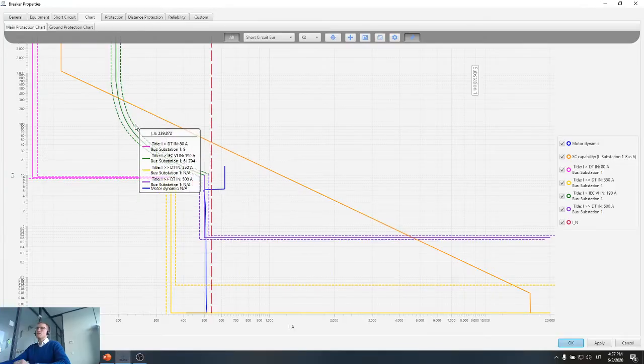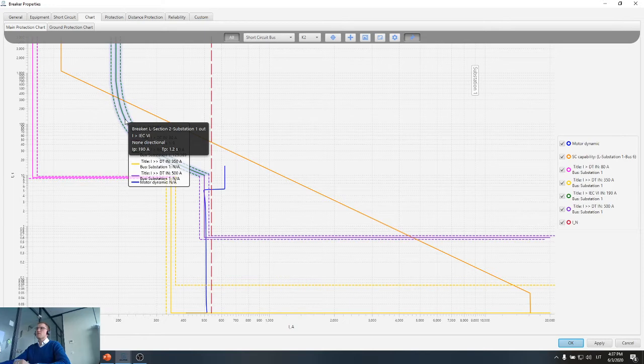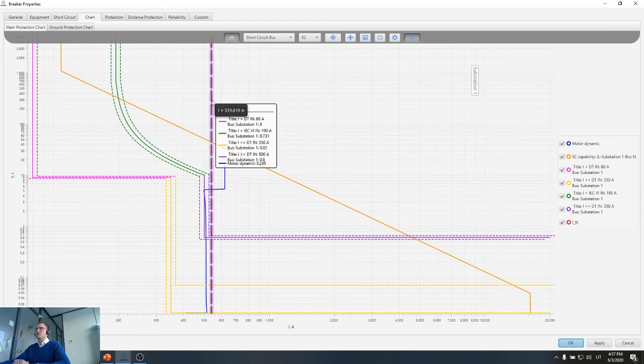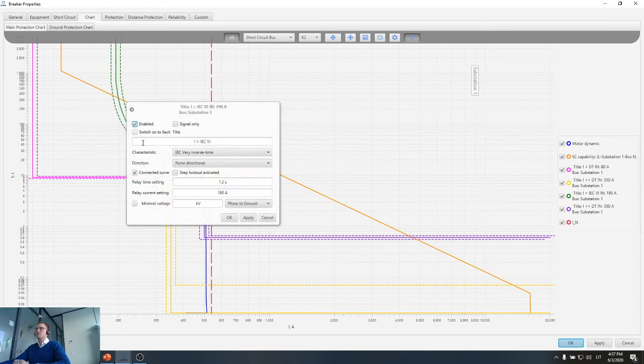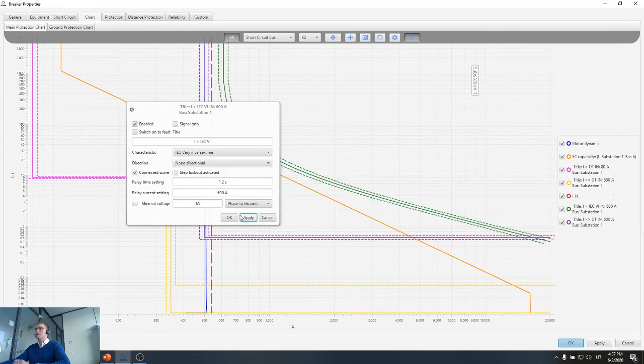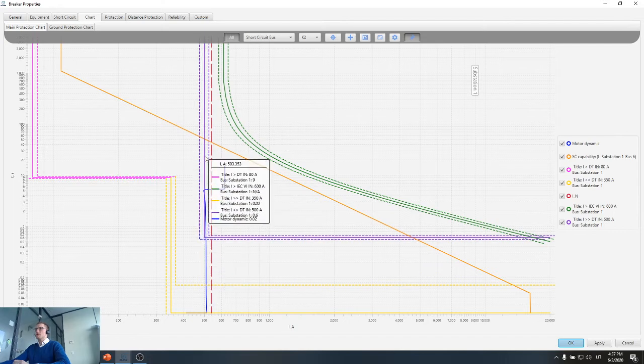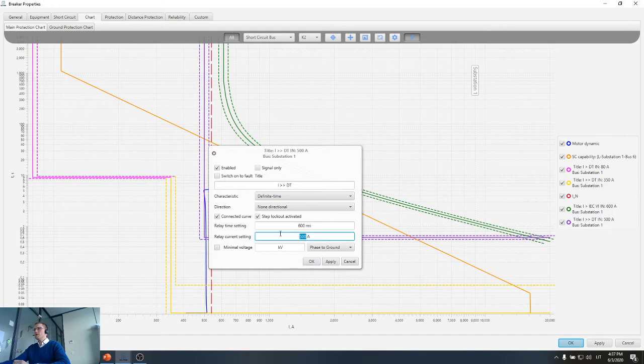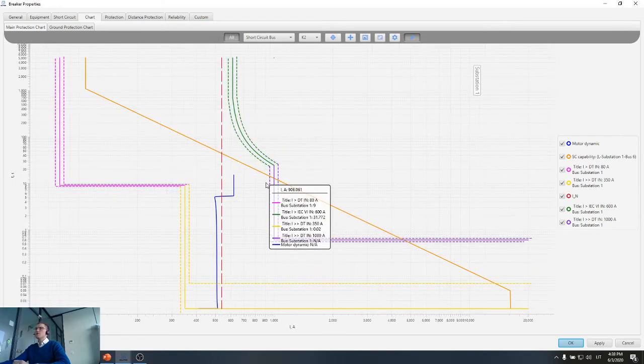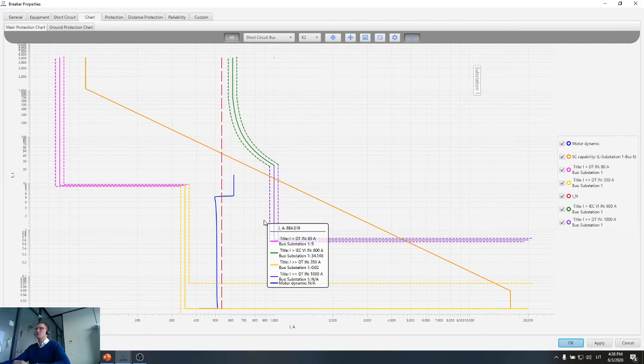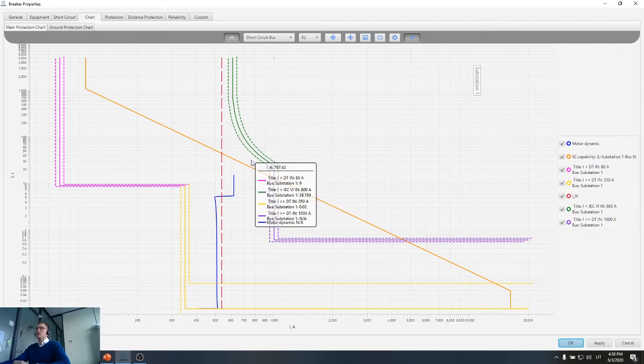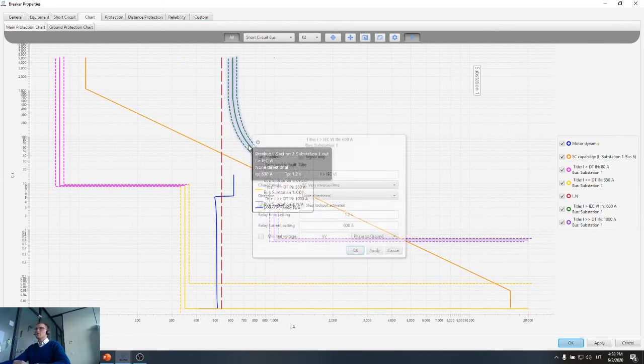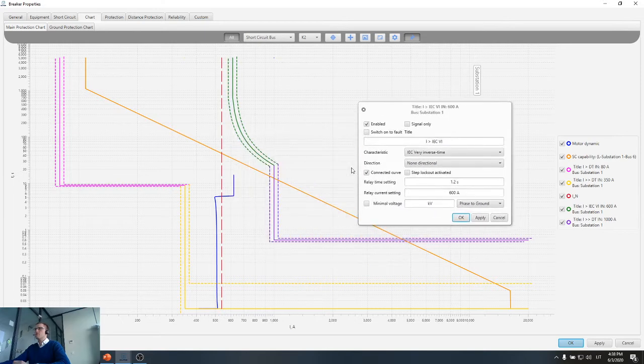So in order to solve this, we need to increase the settings of the relay. First of all, I need to increase the settings of the first stage, so I will provide something like 600 amps with the generator, and then I need to increase the settings of the second stage, so I will provide something like 1000 amps. Now my incomer relay will not trip during normal operation of the system. In order to protect the cable, I also need to reduce the time setting for the very inverse time curve. So I will provide a time setting of, let's say, 0.5 seconds.